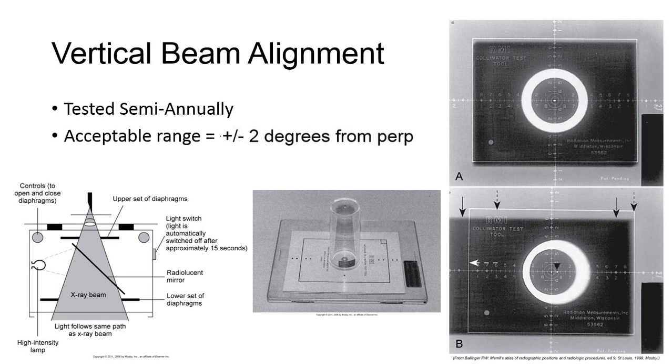This should be tested semi-annually, and acceptance limits are ±2 degrees from perpendicular.